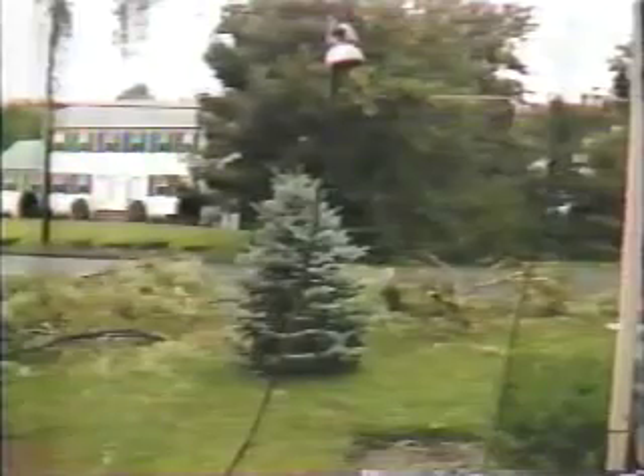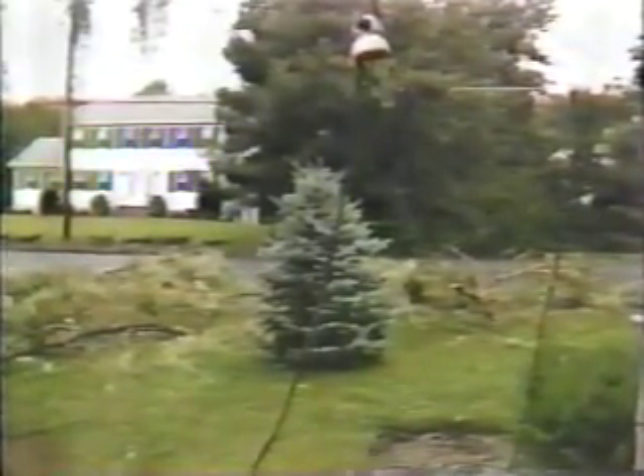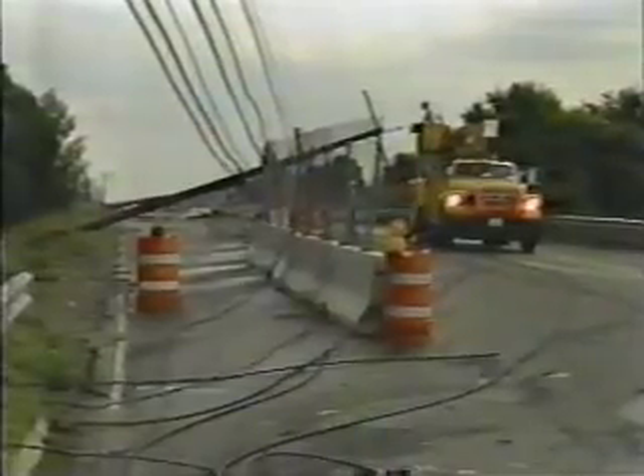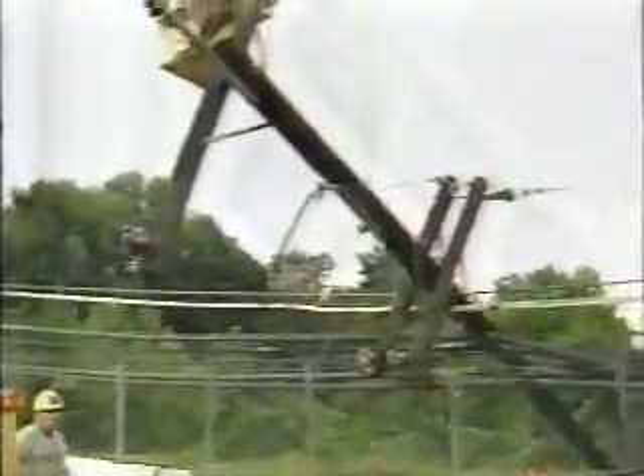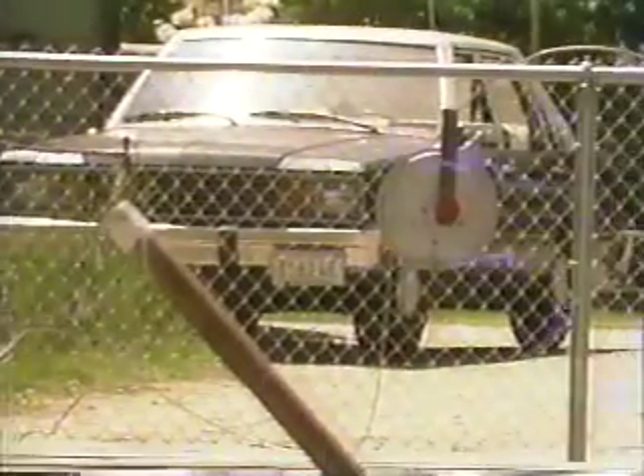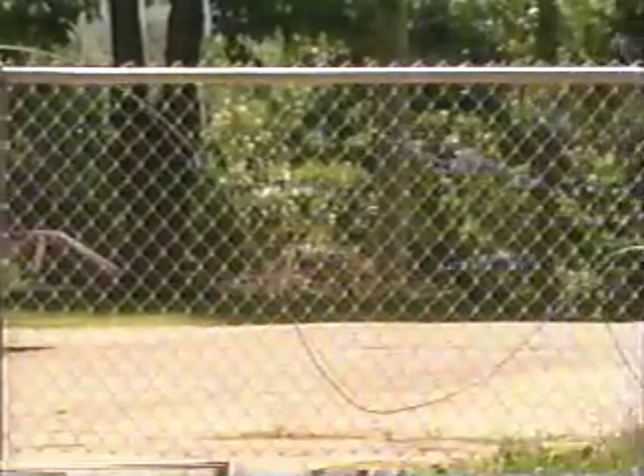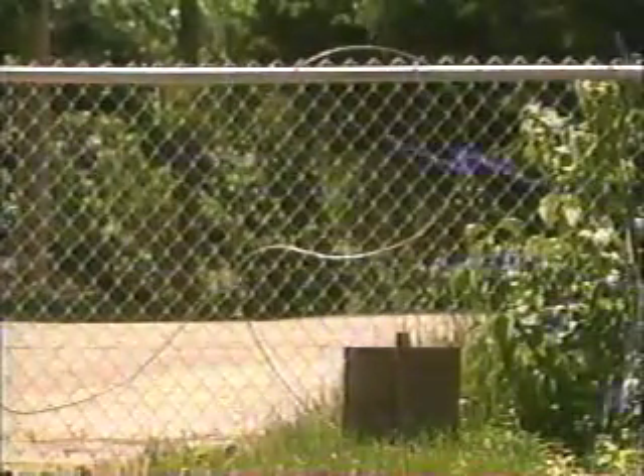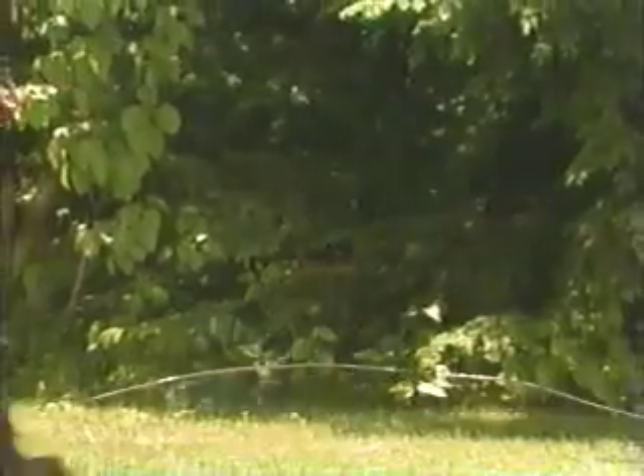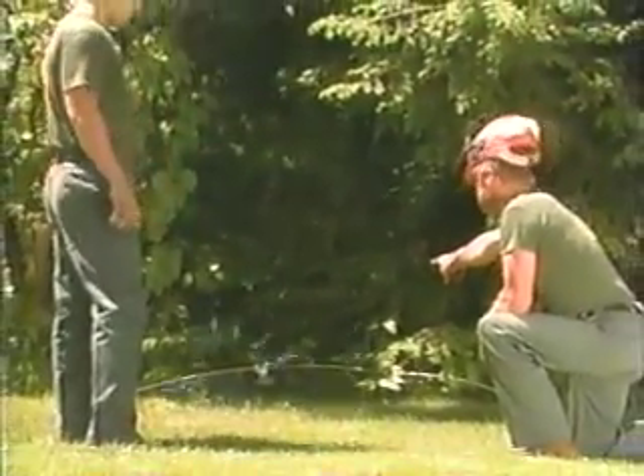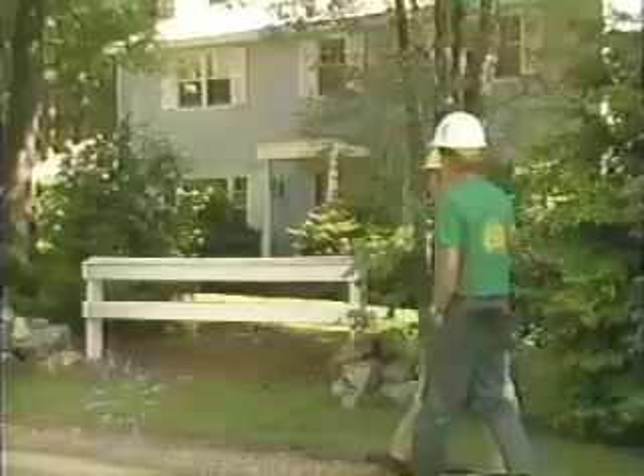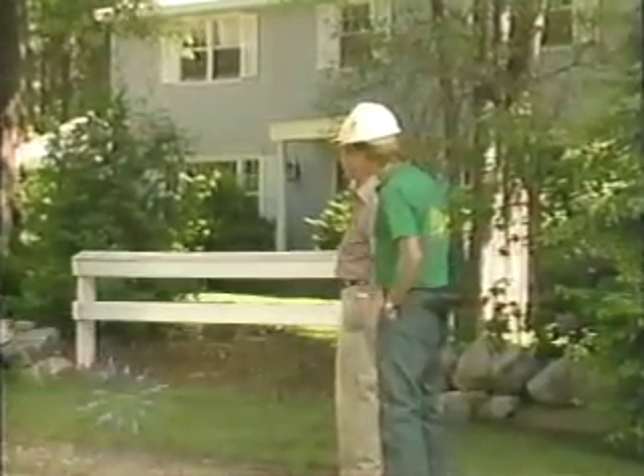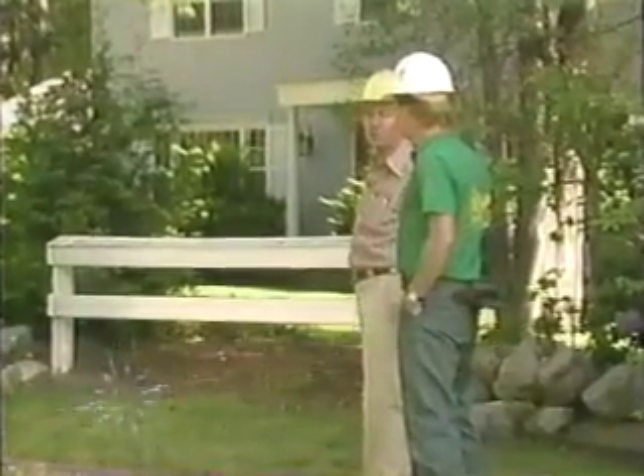Operations aloft and on the ground during storm emergencies can be very hazardous. Routine tree work shall not be performed during the actual storm, and workers doing storm cleanup should be aware of the following. Fallen conductors can energize the most unexpected items, such as chain link fences, guy wires, highway guardrails, and even fallen limbs. Always check for the location of any fallen conductors, and assume each is energized until a representative of the utility tells you that conditions are safe, and you can see that both ends of the conductor have been cut and the conductor removed from possible contact with any other energy source.